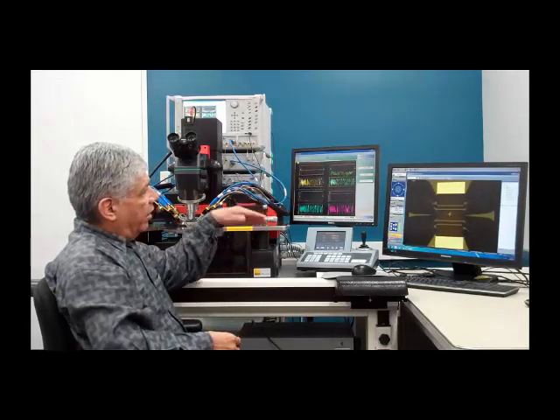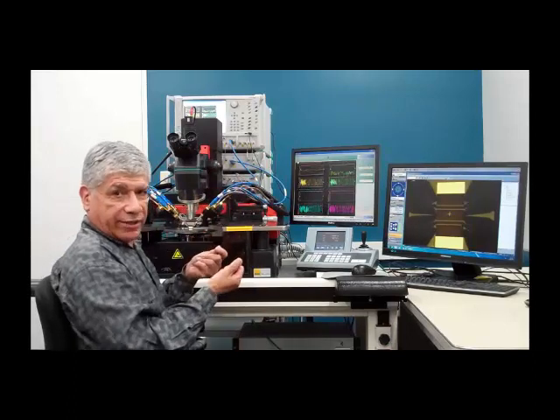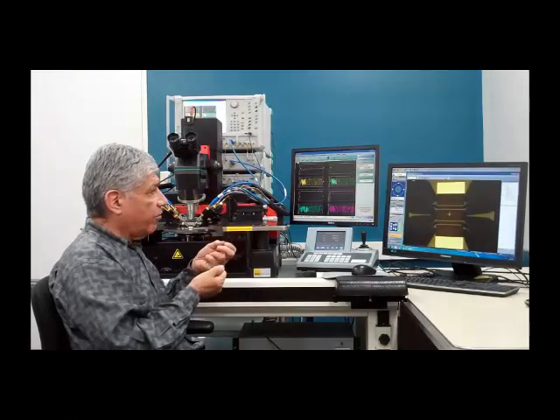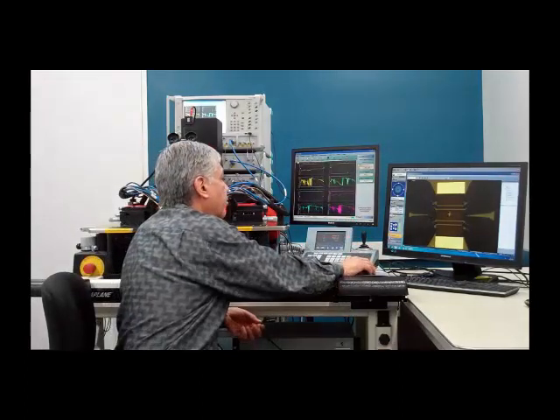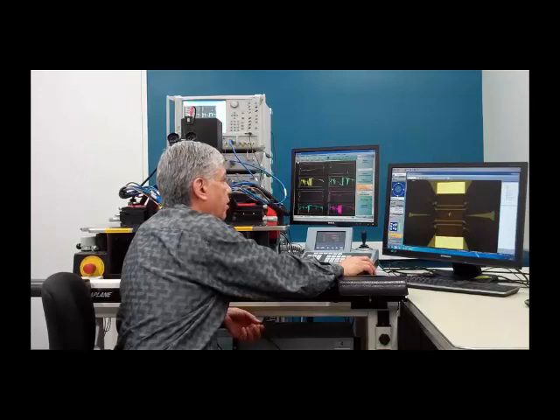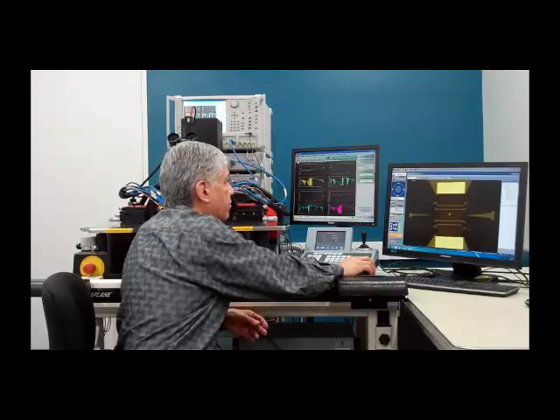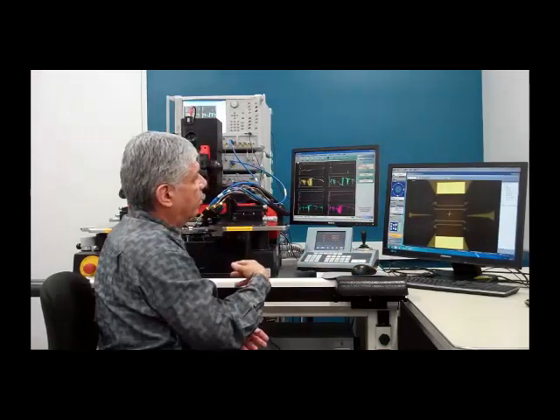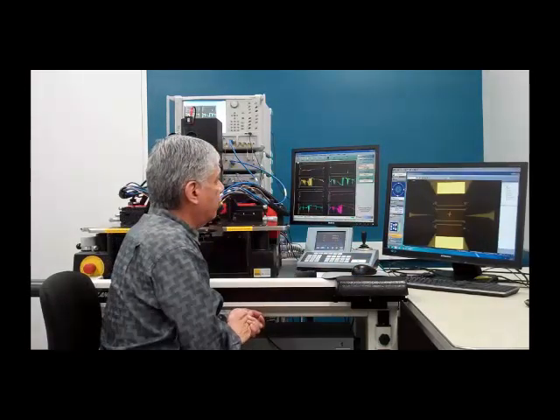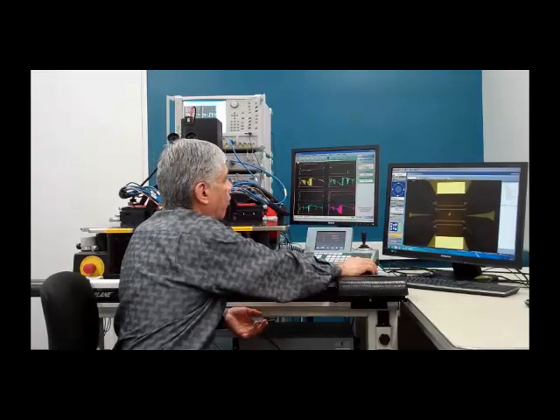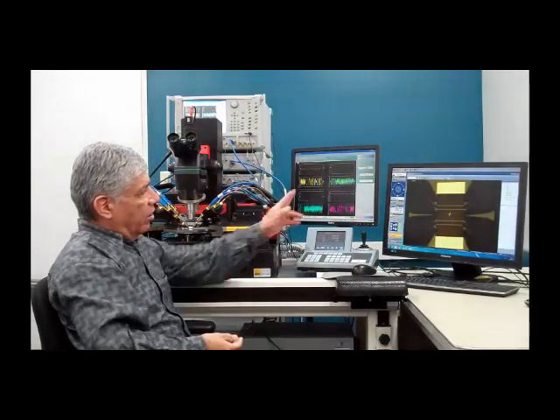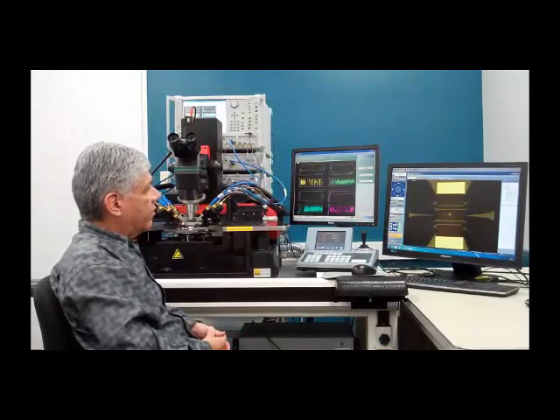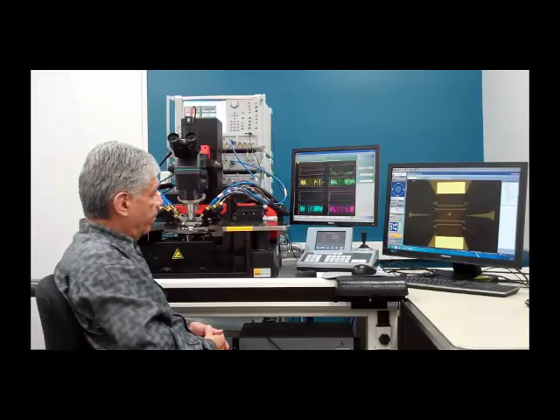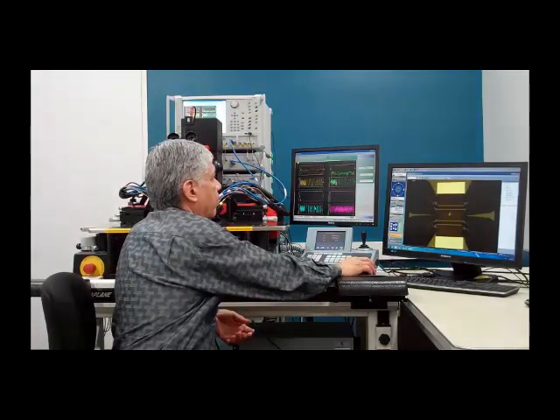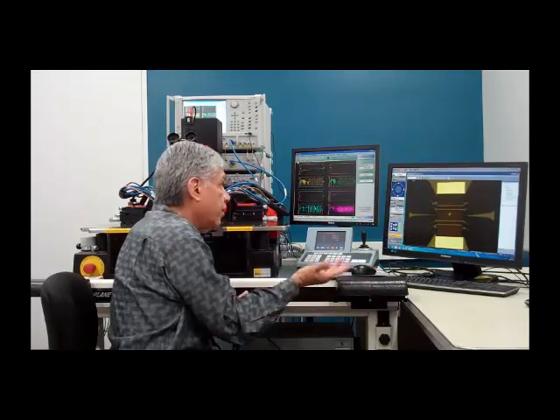And when you do your through connections, they typically will take more time because there's a lot more processing. You're basically looking at a number of different characteristics of the standard in order to extract out all the error terms in your system. And so now we've finished with the port 2, 3, and we've gone over to the ports 1, 4, and we make a measurement of ports 1 and 4 of the standard. And then once it's finished with that, then we're done.